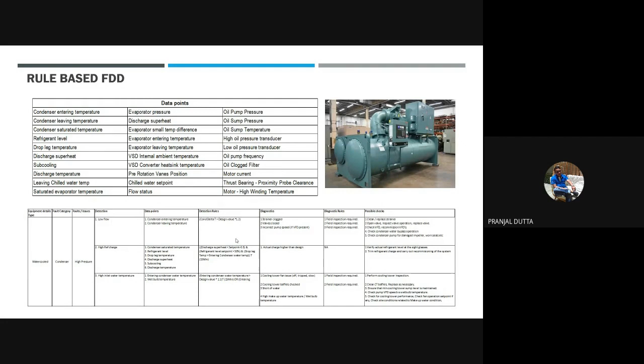So this is called FDD. This is very straightforward. There is no ML used in this particular application. To write the FDD, you need to know the entire system very well. For a chiller, I have given some parameters, like reduced condenser water flow. It has implications for other parameters, like the instantaneous input power. Green means it will increase, red means it will decrease, and zero means there is no effect from this particular change in the parameter.